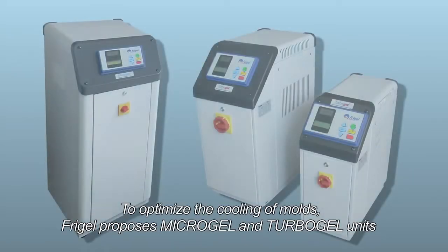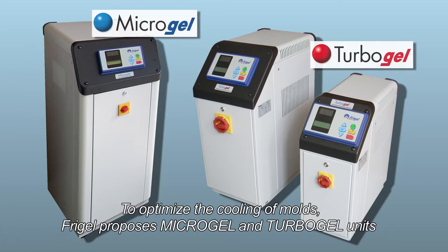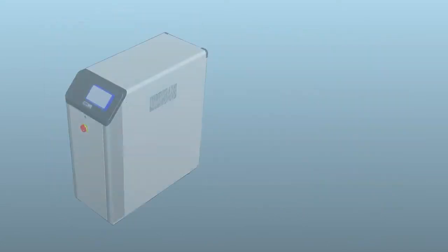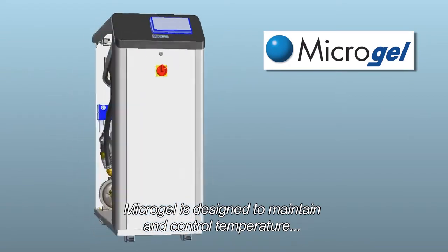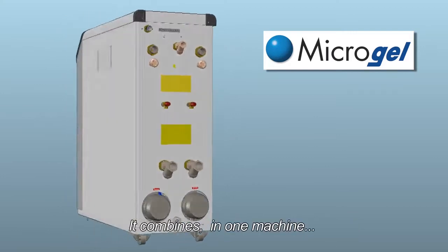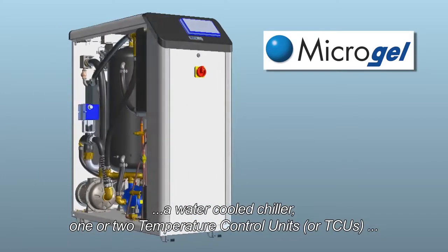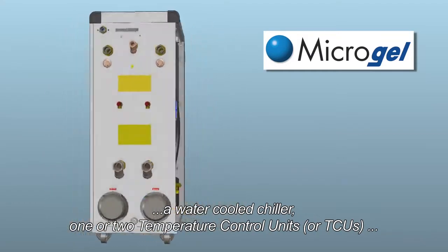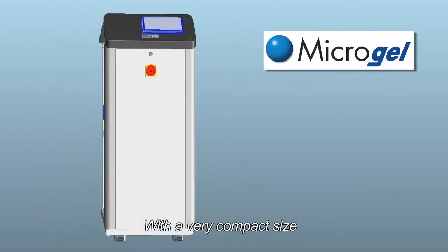To optimize the cooling of molds, Frigel proposes Microgel and Turbogel units. Microgel is designed to maintain and control temperature, pressure and flow of water through a mold. It combines, in one machine, a water-cooled chiller, one or two temperature control units, or TCUs, and a free cooling valve, with a very compact size.